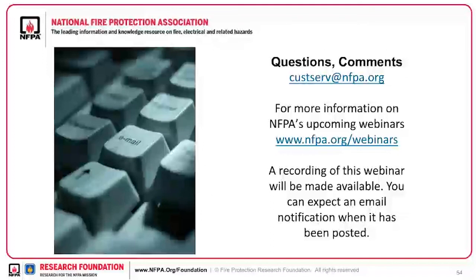The last question: can you summarize the prescriptive versus performance-related protection requirements in the upcoming NFPA 855? The shortest way to do it would be adequate space separation, and it's a combination of sprinkler protection and space separation. So 0.3 gallon per minute per foot squared sprinkler density, coupled with 3-foot space separation for systems that are less than 50 kilowatt hours.